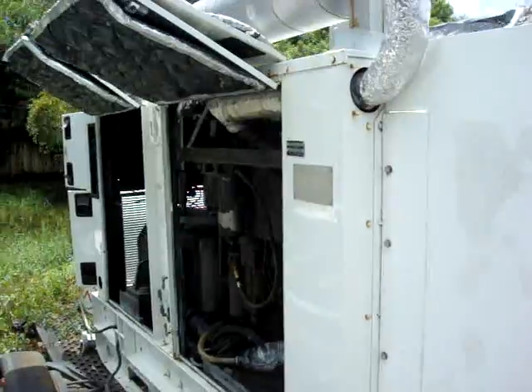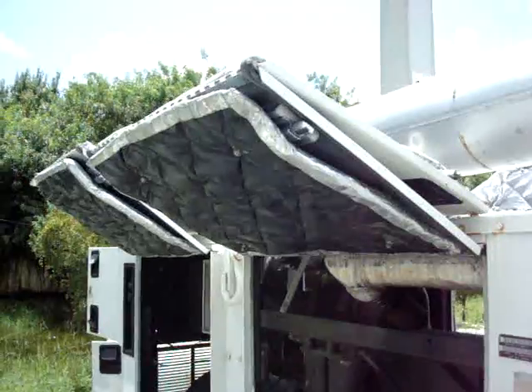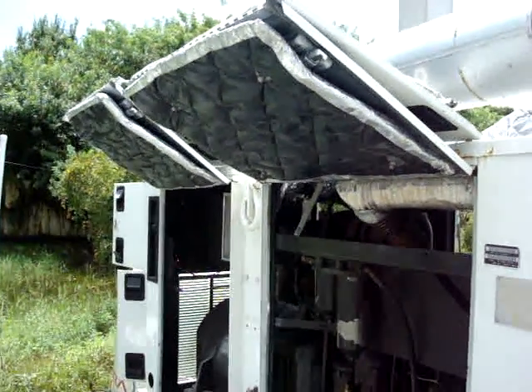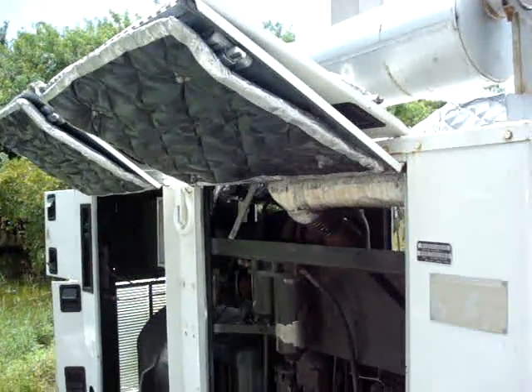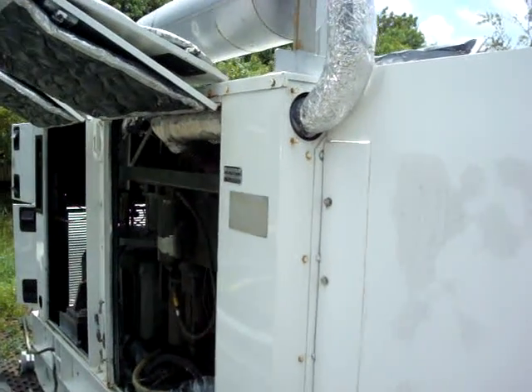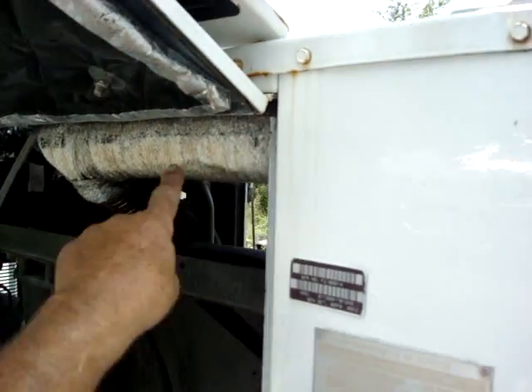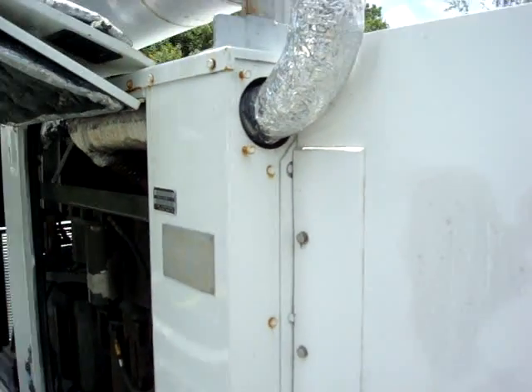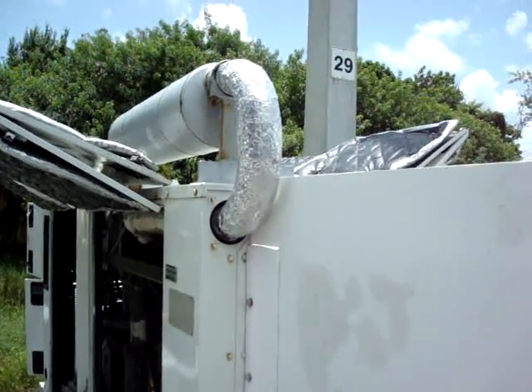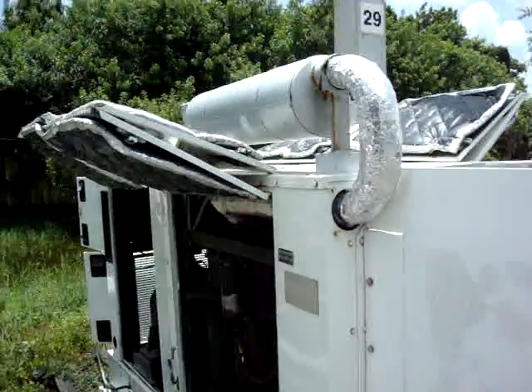A lot of improvements have been made, not the least of which is the fiberglass and lead insulation that lines the entire inside. Of course, these doors during operation are fully closed. The original unit comes with a spark arrestor in this location here, but that's been eliminated and insulated and replaced with a diesel-rated muffler.